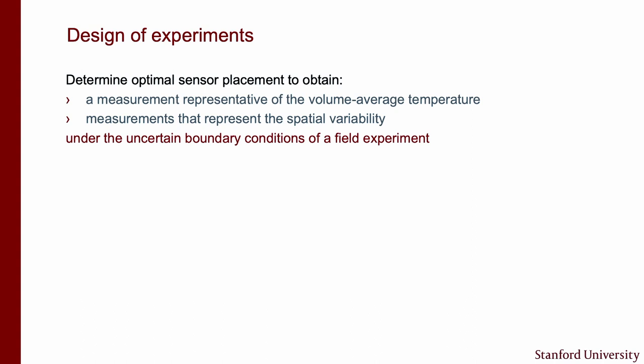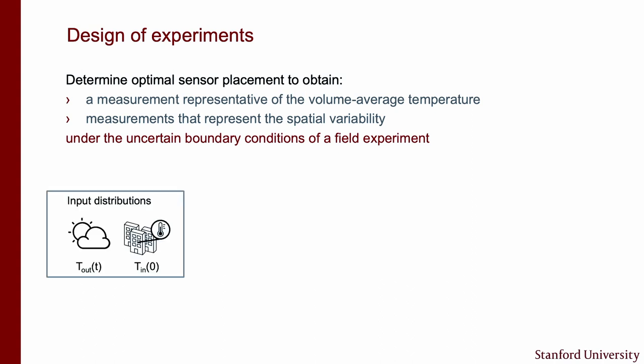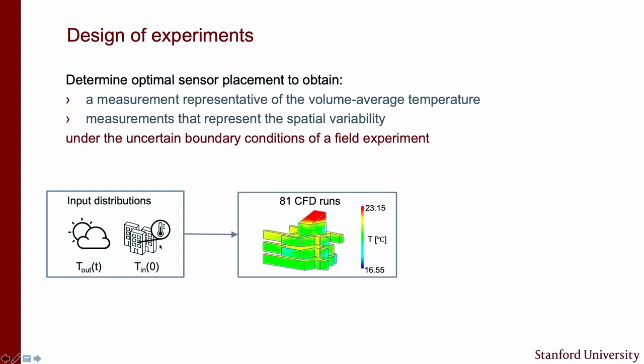That brings us back to uncertainty quantification. We can look at historical data for the outdoor temperature and the indoor temperature at the start of the ventilation process, and fit distributions to what these parameters are going to be. These distributions define the boundary conditions for our CFD simulations, and we propagate these uncertainties using polynomial chaos methods.